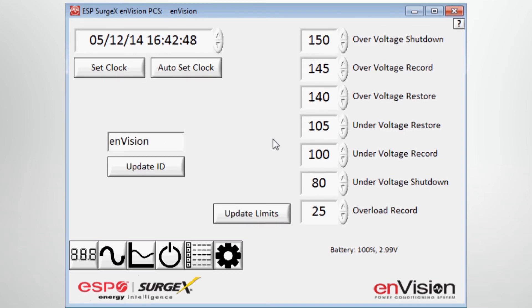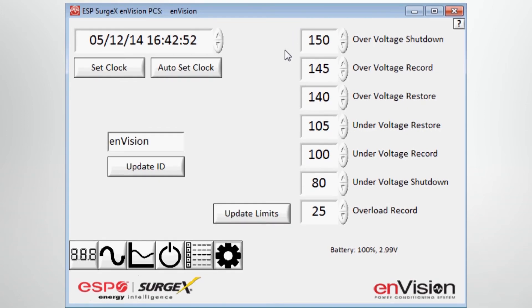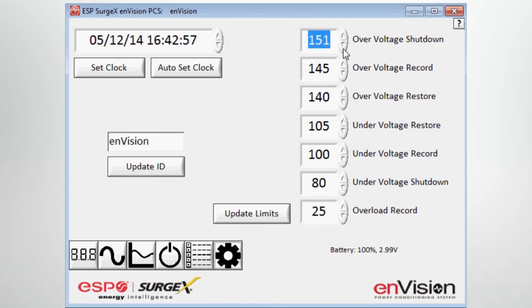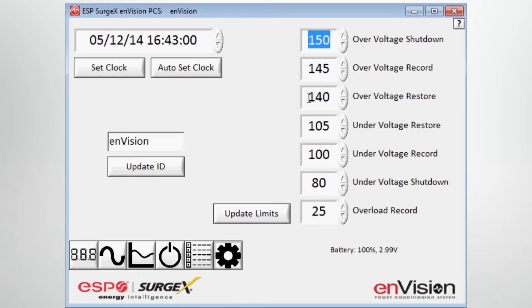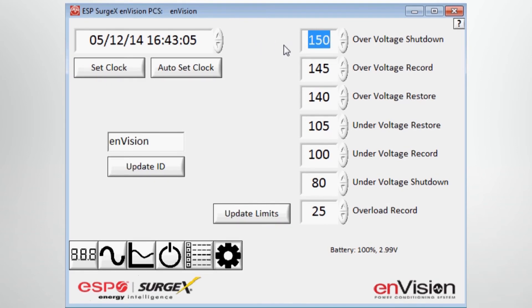And then on the right hand side, you see here you have the ability to change the factory settings for the overvoltage shutdown level in one volt intervals, the overvoltage record level in one volt intervals, and the overvoltage restore level, which means if my device is set to turn off, if I see a sustained overvoltage at 150 volts, I want it to restore when the line voltage reaches a safe voltage of 140 volts.